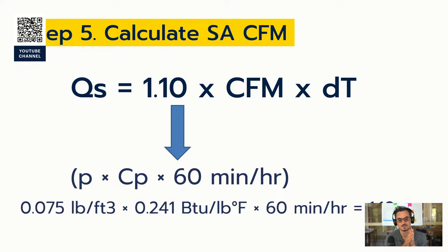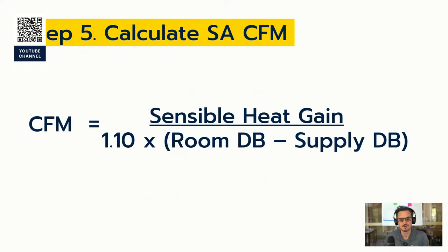So the density and specific heat of air will change depending on where you're at. Where we're at here in Asheville, we're, I don't know, 1,000, 2,000 feet, depending on where you're at. It doesn't change that whole lot if you're doing commercial air conditioning. If you're doing something extremely critical, pay attention to that. If you're in Denver, you better pay attention to that, because this can get you in a lot of trouble. So make sure that you know what you're dealing with wherever you're at.